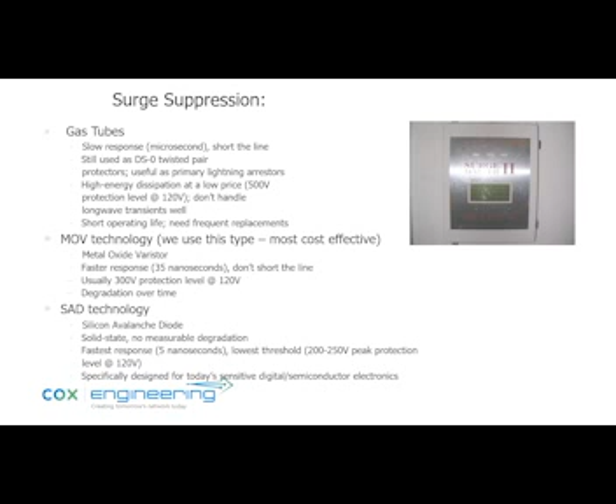So with surge suppression, you think of surge suppression at the critical facility level, at the AC electrical panel level, and of course, even at the circuit level, anywhere from gas tubes to metal oxide varistor technology to silicon avalanche diode. They all have their pluses and minuses in terms of how quickly they work to suppress the surge, and also whether they are killed instantly or you can actually use them over again.